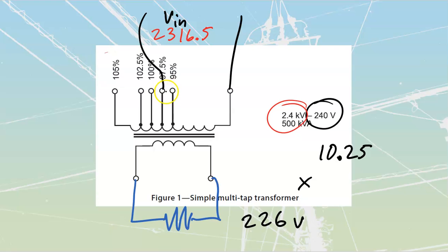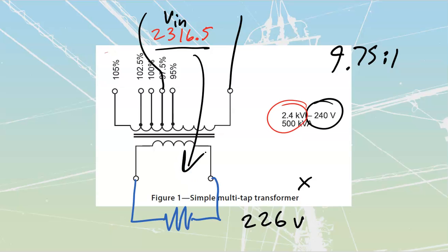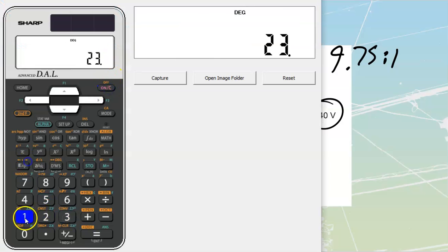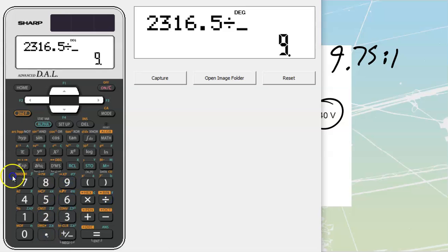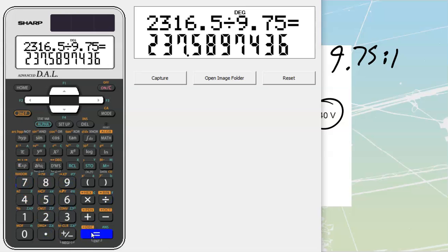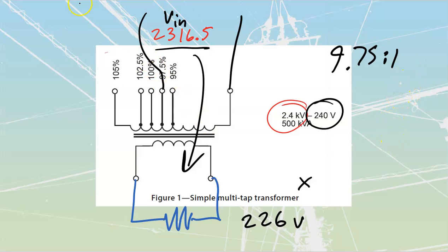If I'm at the 97.5%, that means that my turns ratio is actually 9.75 to 1, which means that the voltage I'm going to see on this side is going to be 9.75 times smaller. So I'm just going to take 2316.5 divided by 9.75. That's going to get me to a value of 237.6 volts. So by moving down to here, we get rid of this 226, we move to 237.5 volts, like that. This is the way that in the field we do most of our calculations.